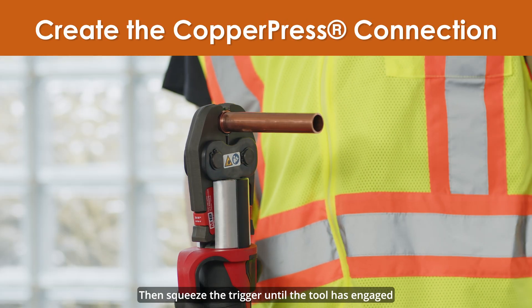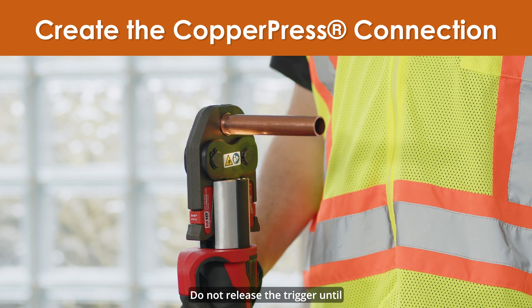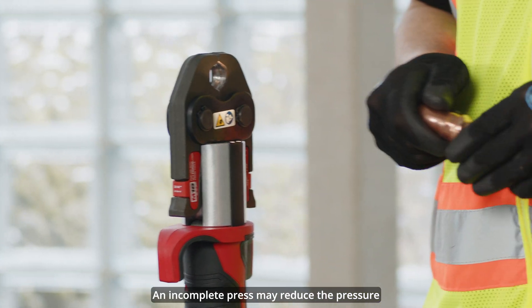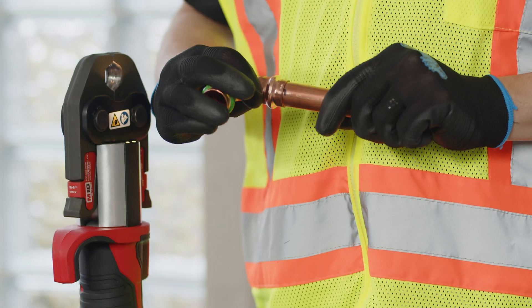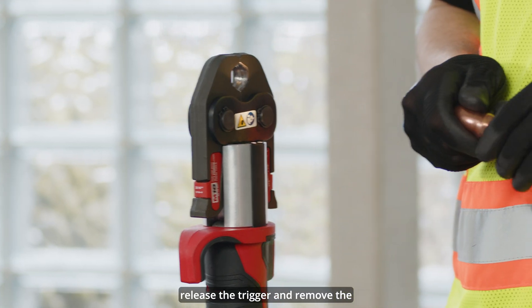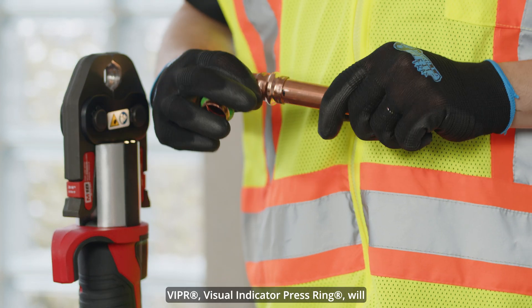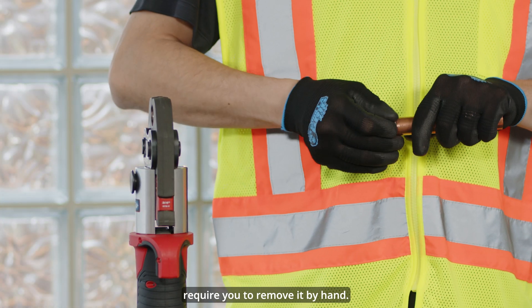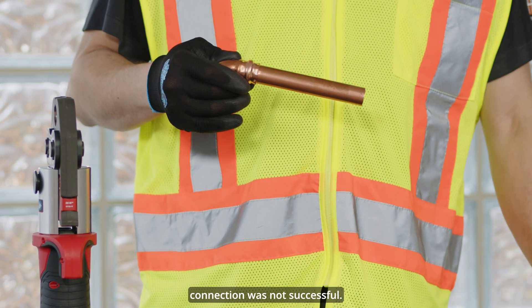Then squeeze the trigger until the tool has engaged the sealing element or VIPR visual indicator press ring. Do not release the trigger until the pressing action is complete. An incomplete press may reduce the pressure retention capabilities of the joint and lead to subsequent system leakage. Once the tool has completed a full pressing cycle, release the trigger and remove the jaw from the fitting. After the jaw is removed, the VIPR visual indicator press ring will break off indicating a complete press. Note that the VIPR may require you to remove it by hand — this does not mean that the connection was not successful.